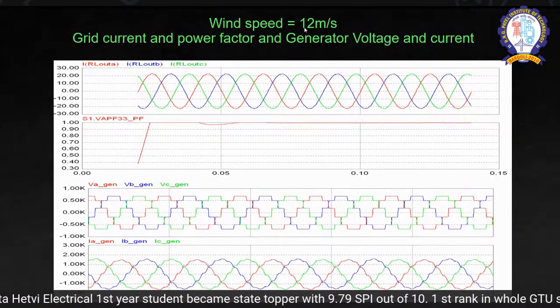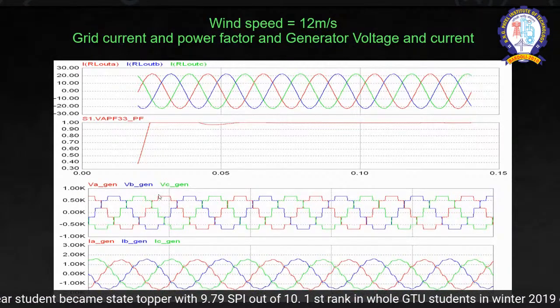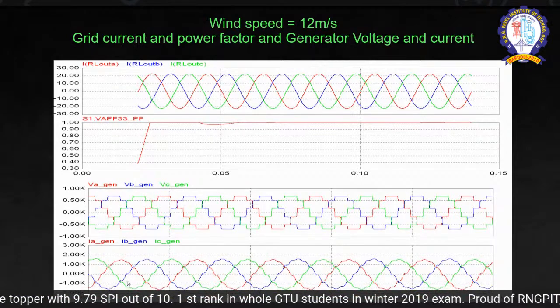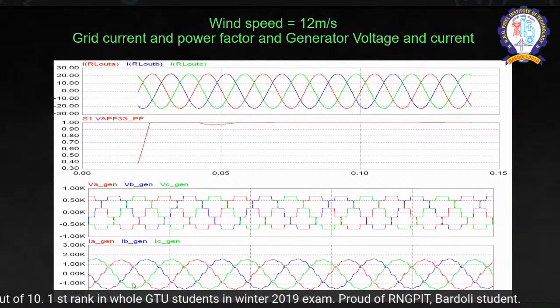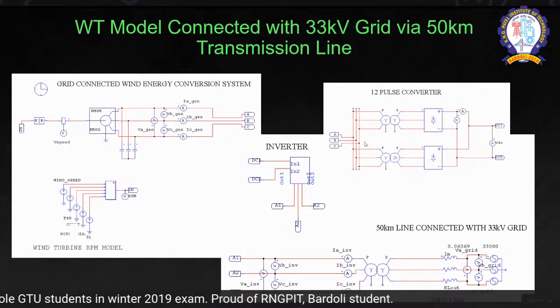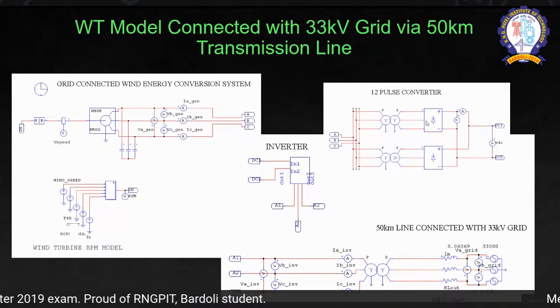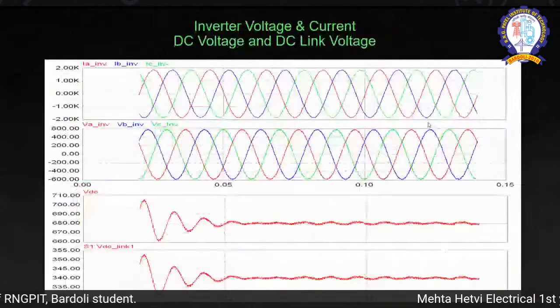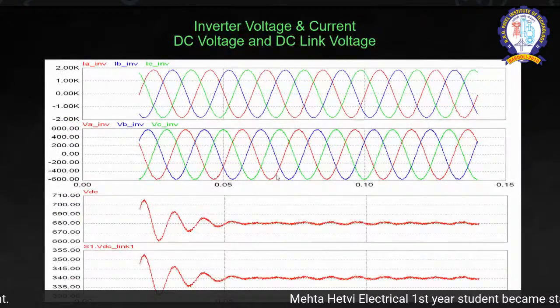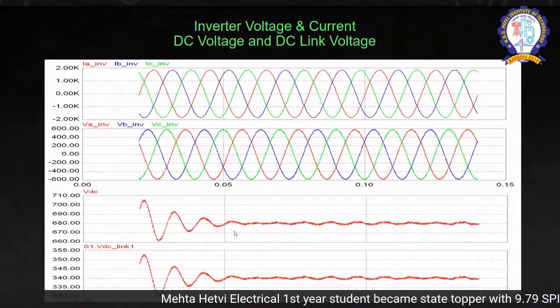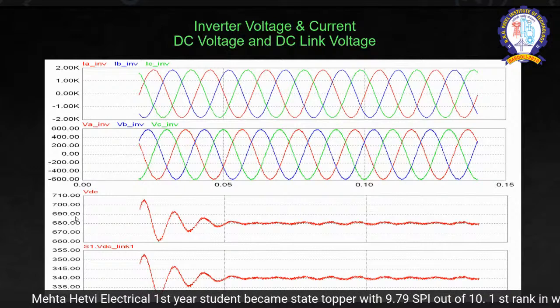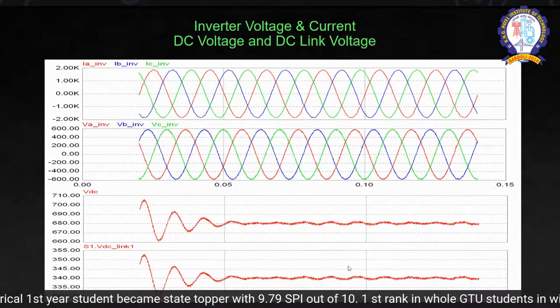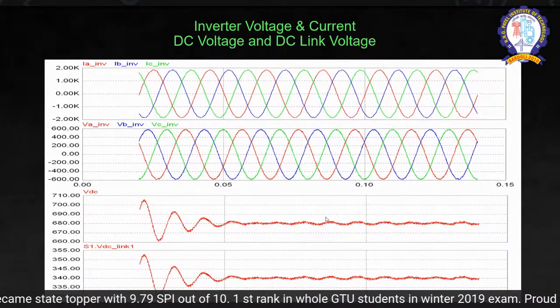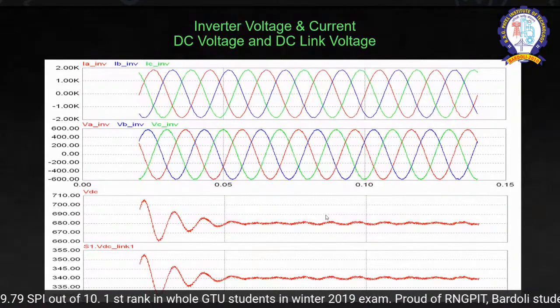This is tested for 12 meters per second. This is the generator voltage and generator current. It is enriched with some harmonics because over here, this 12 pulse converter is not in closed loop. This is the inverter voltage and inverter current. This is the DC link voltage and DC link current, which is around 680, because at 680 plus or minus 10% limit, this is the voltage of the inverter window.